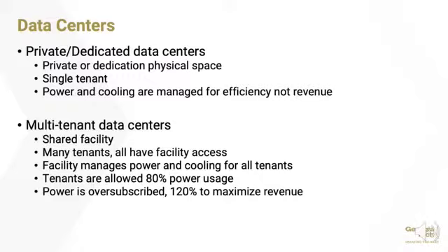This is possible because most servers in the data center are not running at full capacity, thus are not using their maximum allotted power. Power oversubscription is common and is a powerful tool for increasing utilization and revenue while reducing capital costs. But the drawback is that it can potentially create dangerous infrastructure vulnerabilities.